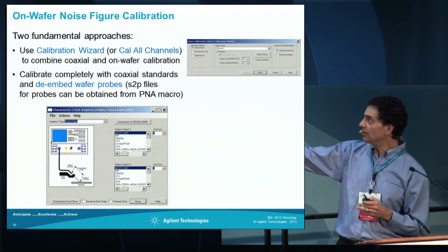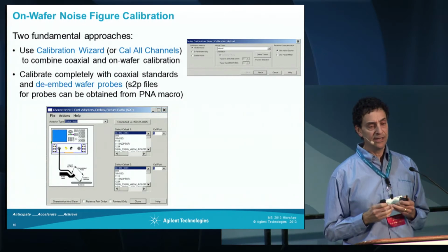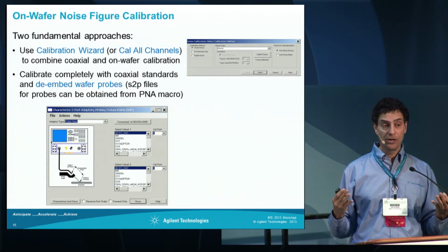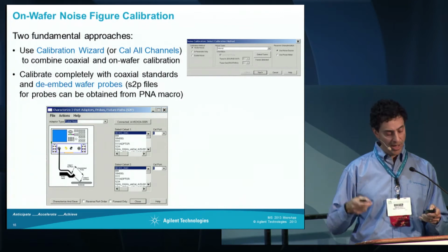With this approach here, you're not having to disconnect anything, but it means you have to go through a full wafer probe calibration. So the choice is yours. Either way works.